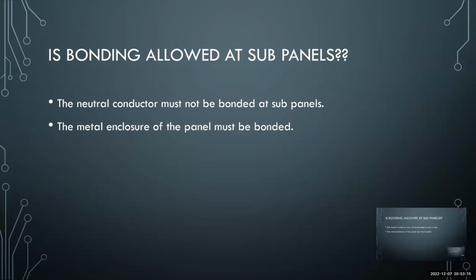Hey, Mike. Yes. Someone has seen Ufer ground copper coming out of the floor, presumably attached to the rebar in the footing. Does it need to be welded before it's buried in that case? No, they make a clamp that's listed for encasement in concrete, and it has to be listed for that. So it can be clamped and then concrete poured over it. So no, it doesn't have to be welded. There's also exothermic welding that's suitable, and certain irreversible crimp connectors can be used, but it can be a clamp.